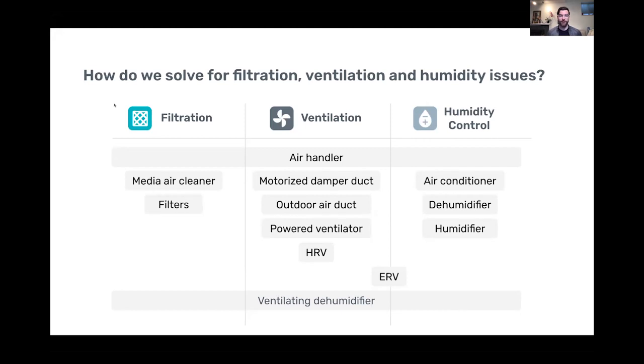And so with ventilation, you have something as simple as just bringing in outdoor air as the air handler is running passively, and that can be a certain minimum CFM, which might be defined by ASHRAE 62.2. But you can also put a motorized damper on that outdoor air duct for the ability to either bring in more air than the minimum to offset a higher chemical event or a higher period of occupancy, and then turn it down to the minimum, or even turn it down temporarily to off if you have a demand control ventilation system. So that motorized duct is important.